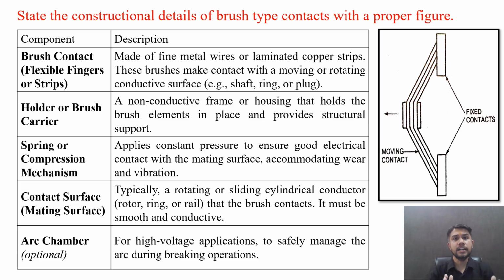State the constructional details of brush type contacts with a proper figure. So there are several components in this, and its description is also given. First is the contact itself, that is the brush contact. These brush contacts have a flexible finger or strip, made up of fine metal wires or laminated copper strips. These brushes make contact with a moving or rotating conductive surface, that is a shaft, ring or plug. You can visualize this brush contact in a DC machine, where carbon brushes are placed and take the current out to the terminal, providing the current.